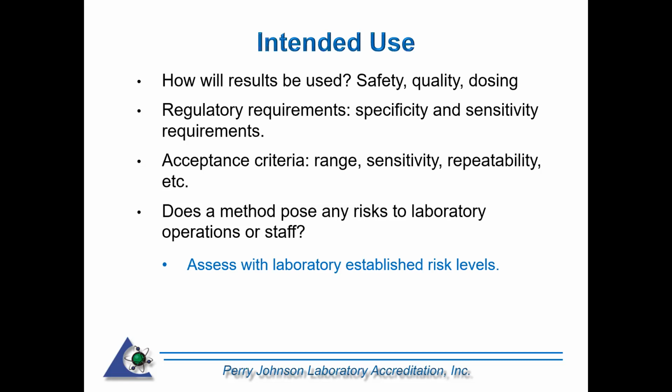Also looking at regulatory requirements. These are ready-made specificity and sensitivity requirements. The challenge is that they are probably different in every single state. So it's really important that in your individual state, you make sure that you're looking at regulatory requirements. Because this is a young industry, it's also constantly changing, almost weekly in some places. So it is very important to stay on top of that and use that information for looking at intended use and planning your validation studies.